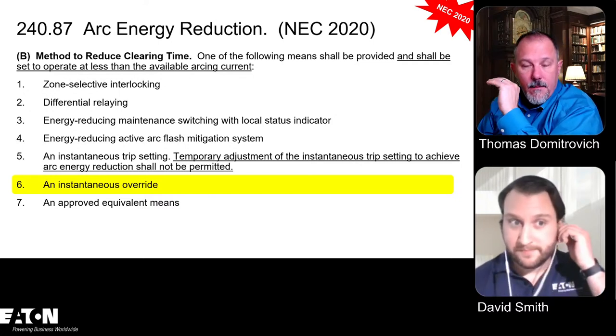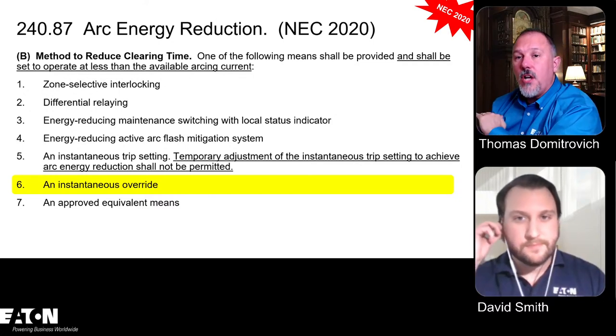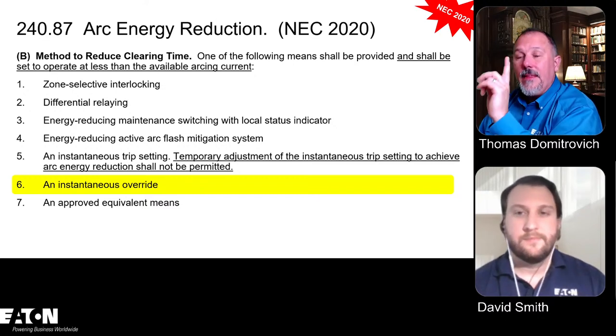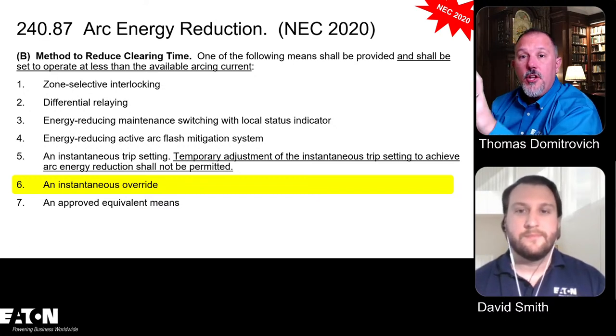Instantaneous override: molded case and insulated case circuit breakers all have an instantaneous override, and that's there to protect the breaker. You just have to look at the manufacturer's instructions to find out what that value is for each of the breakers. So faults in that zone are not provided with protection by the main device instantaneous when the arcing current is in the instantaneous region.